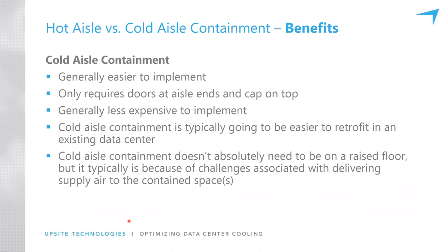Benefits of cold aisle containment: it's generally easier to implement. You don't need the architecture that's required for hot aisle containment. All you have to do is slap some doors on the ends of the aisle and baffles or a roof over the top of the cold aisle, and you've got cold aisle containment. It's generally less expensive to implement for that reason, and it's going to be easier to retrofit for an existing data center.